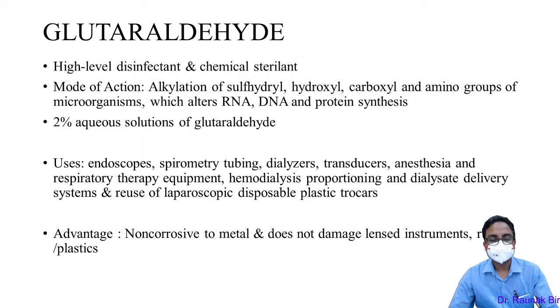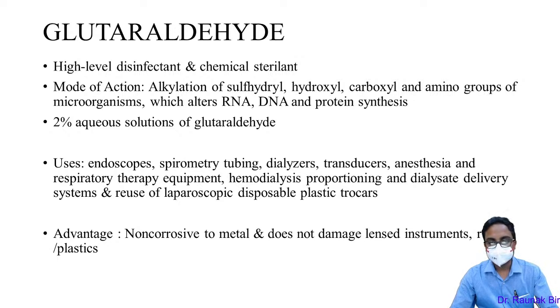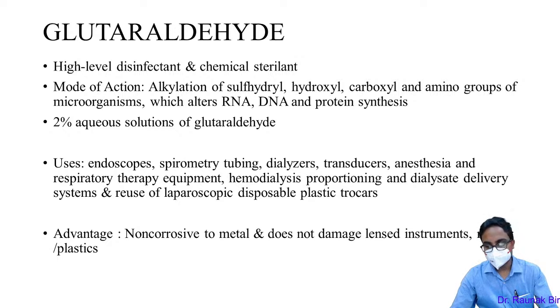The most common aldehyde used in labs and hospital settings is glutaraldehyde — a high-level disinfectant and chemical sterilant. Mode of action: alkylation of sulfhydryl, hydroxyl, and carboxyl groups, causing RNA, DNA, and protein alteration. Most commonly used as a 2% aqueous solution, commercially known as Cidex. All scopes, dialyzers, transducers, anesthesia equipment, hemodialysis equipment, and laparoscopic trocars are sterilized by this method. It is non-corrosive to metals and does not damage lens instruments.